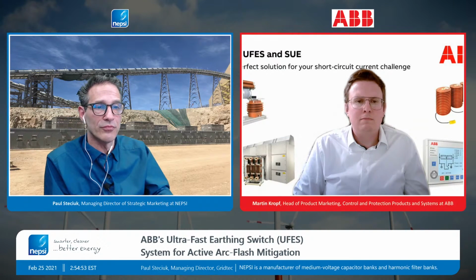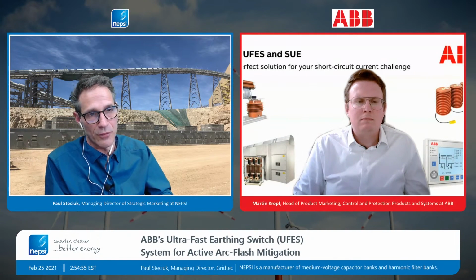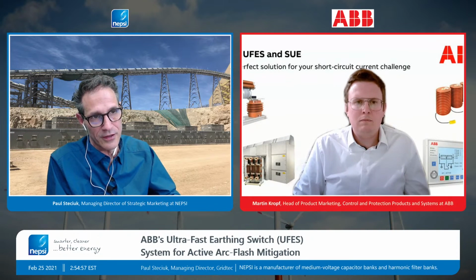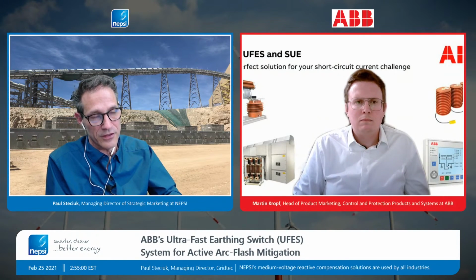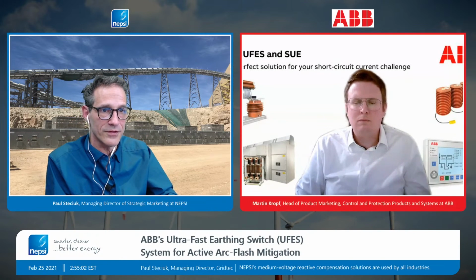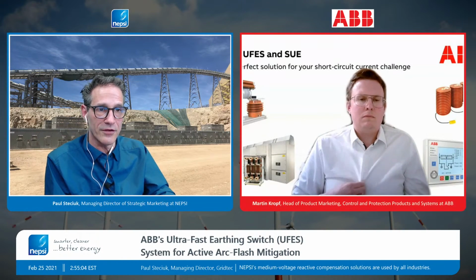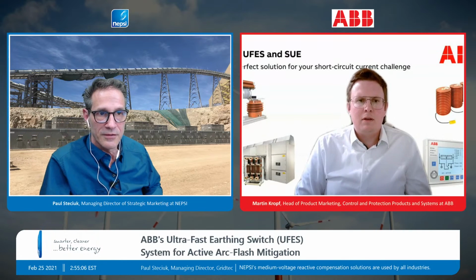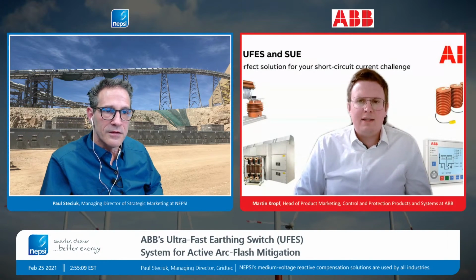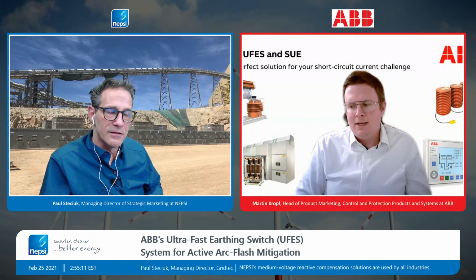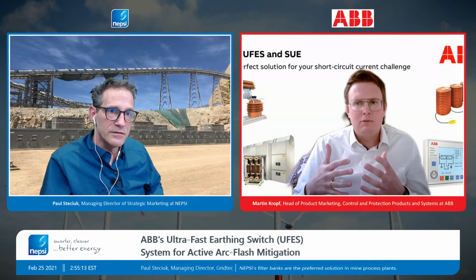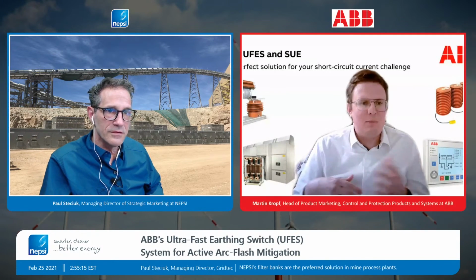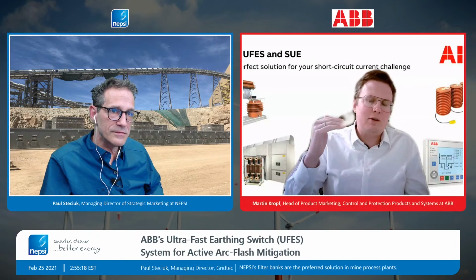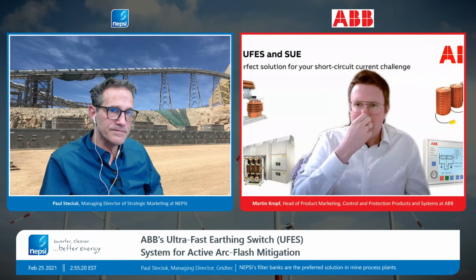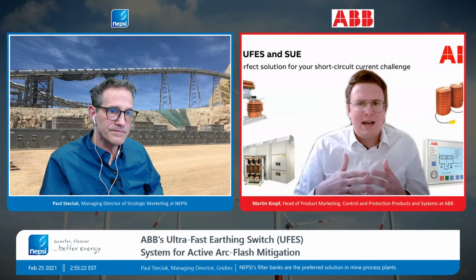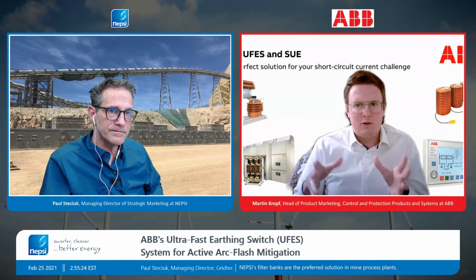If the upstream breaker were to fail and we had to go to a backup breaker and it were to extend, the piece of equipment that the UFES was in would still be saved because the arc has been eliminated from that gear. Would you agree with that? Yes. Absolutely. And maybe to add one point, yes, we need a breaker to interrupt the current. And as you said, Paul, it could be the first upstream breaker, or if this failed, it could be the next one. But we should take this into account when we design the protection zone.